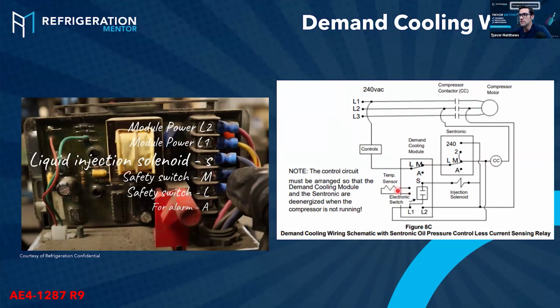You have a sensor right here. So this sensor will go into the head of the compressor. And what will happen is as that sensor starts to rise up in temperature, the resistance starts to change. That resistance will send a signal in here to close this switch. And when that switch closes inside the demand cooling, it's going to say, we need some cooling. It's going to open up the solenoid and inject it in.